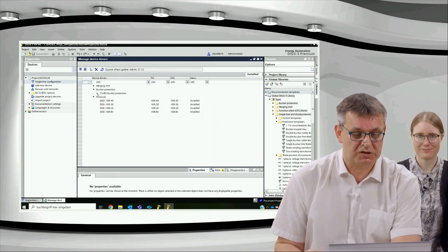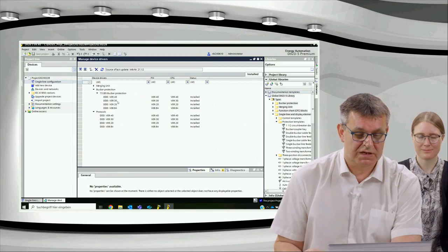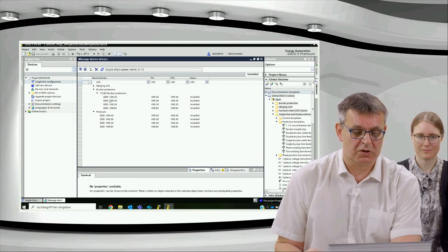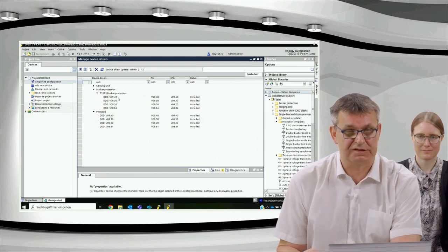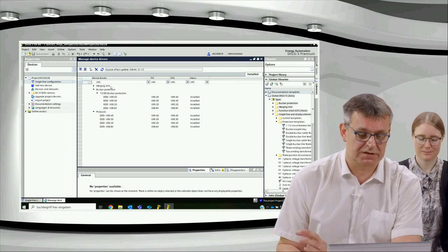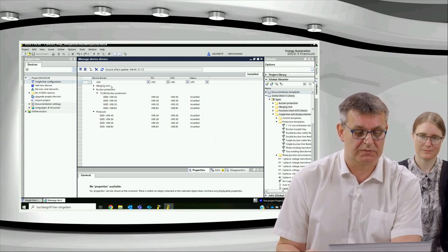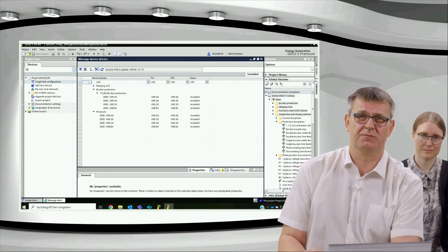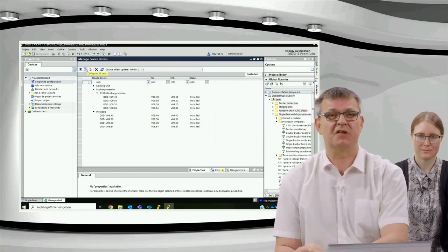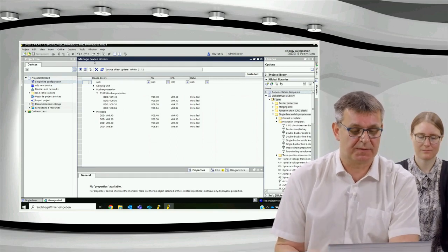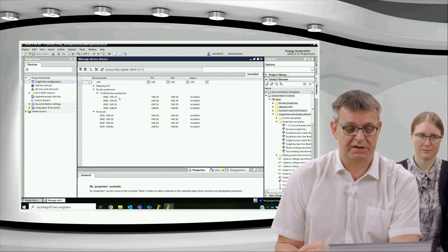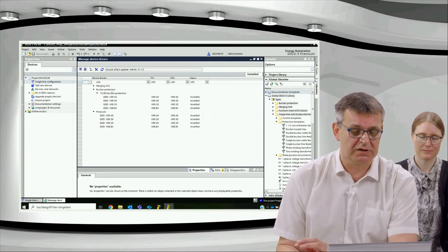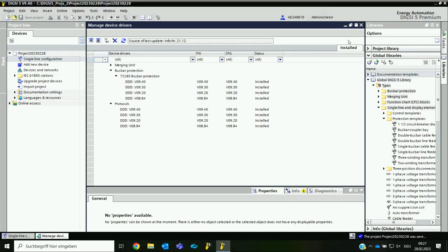And for busbar protection, we have the 7SS85. We have from version 8.84 until version 9.40. 9.40 is the newest one. And I will create for our demonstration, of course, the newest firmware version, the 9.40. But again, it's very important to see really that we have one device which is able to make a centralized busbar protection and distributed busbar protection, and it's only one firmware, one code, one device where you can configure really all different types of busbar protection.